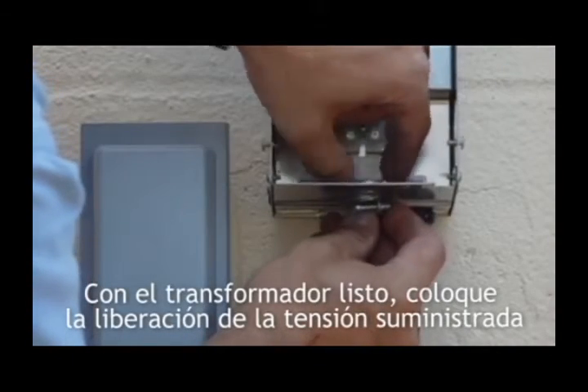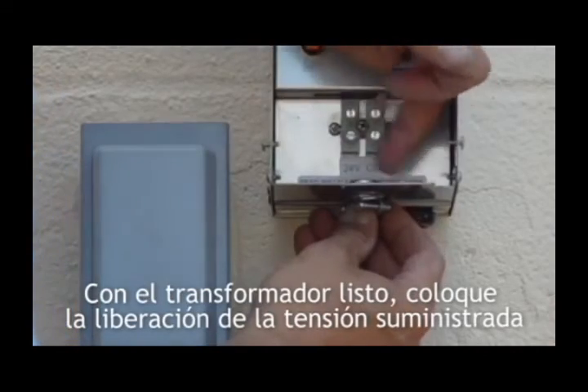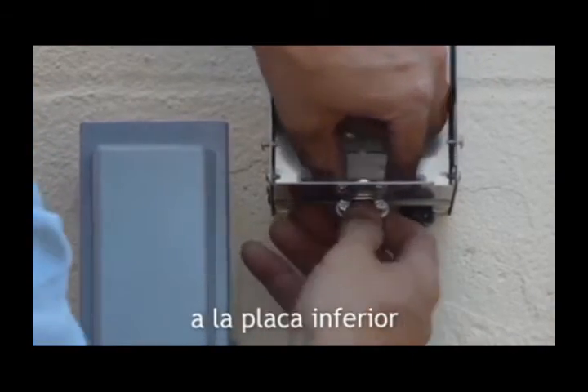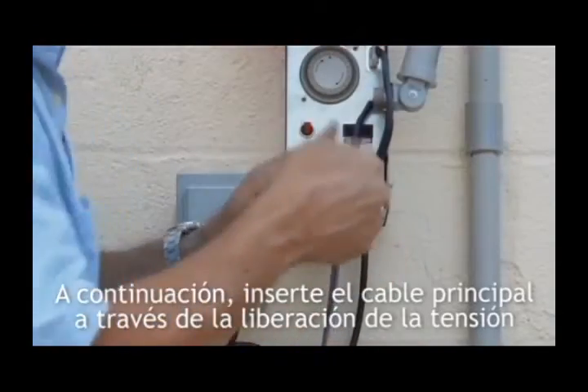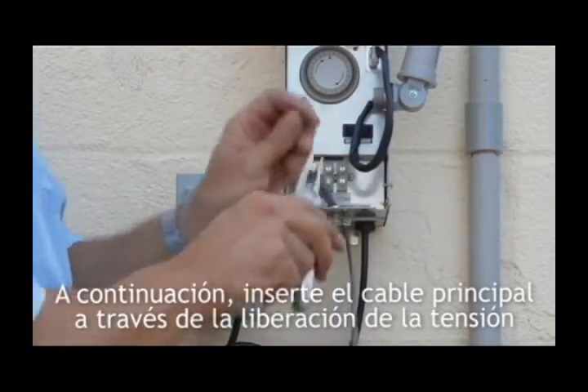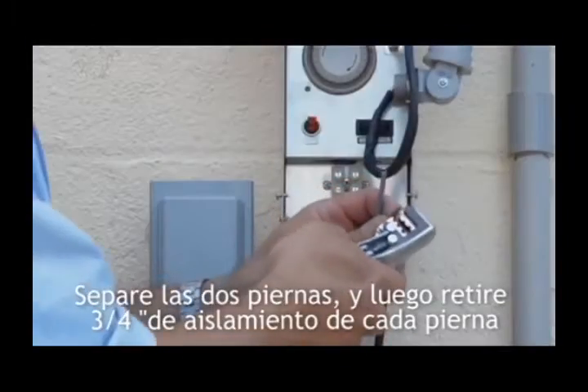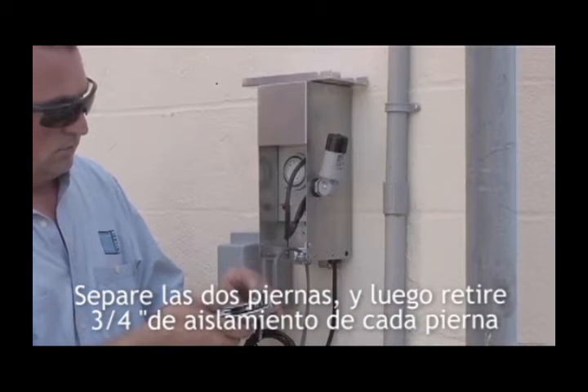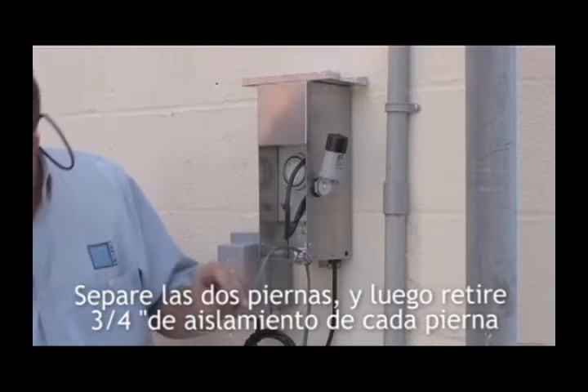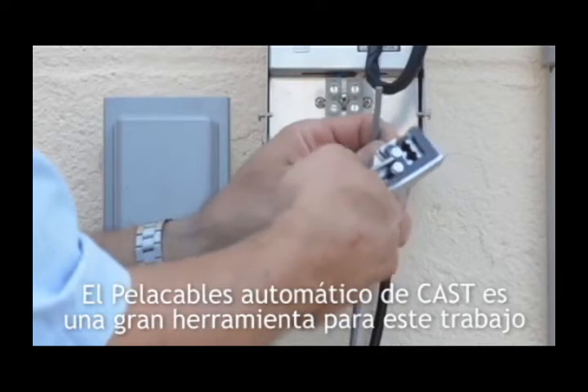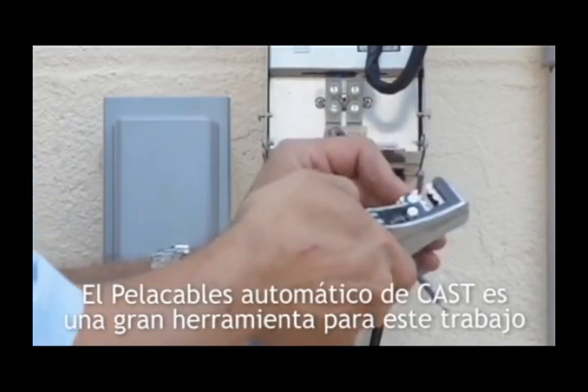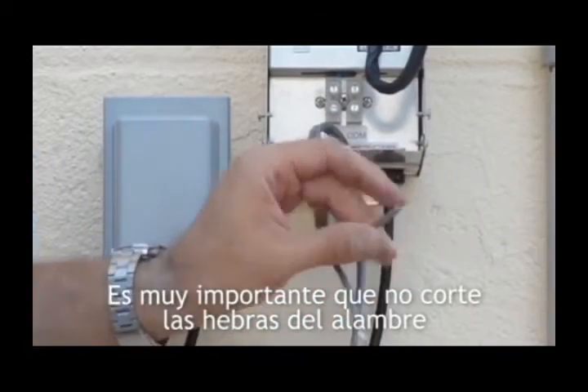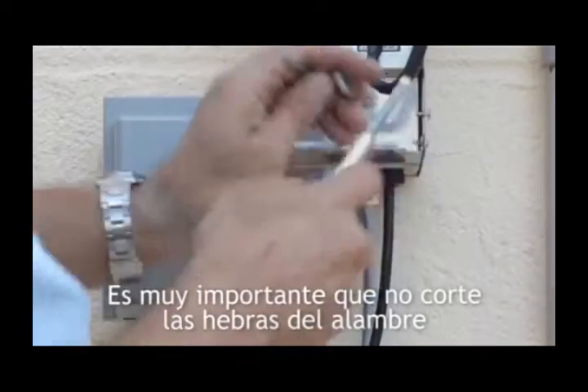With the transformer all set, attach the supplied strain relief to the bottom plate. Then run the home run wire through the strain relief. Separate the 2 legs, then strip 3/4 of an inch of insulation from each leg. The cast automatic wire stripper is a great tool for this job. It's very important that you don't cut any wire strands.